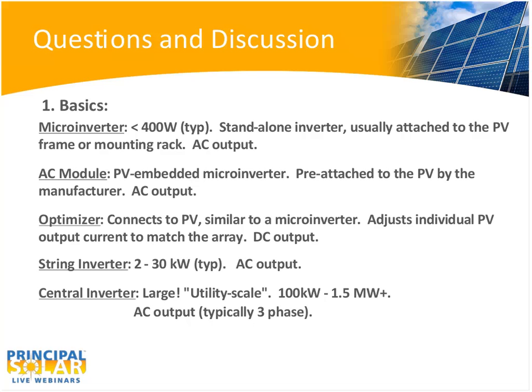Central inverters are large. Typically, they require a crane to move. These are utility scale by definition, typically 100 kilowatts up to 1.5 megawatts or million watts, and some are even getting larger now. They are AC output only, and virtually all are three-phase.